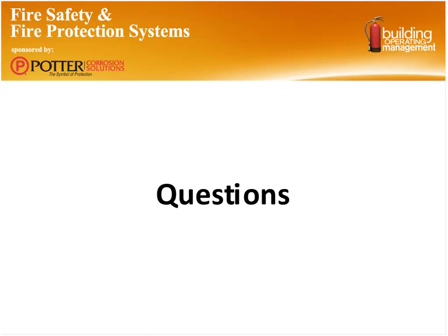One question that came through: who is supposed to inspect fire damper systems? Typically, there's two types. There are a couple of companies out there that are strictly what we call fire door, fire damper testing and inspection companies. They are kind of standalone, and that is their special niche. On the other side, there are traditional door companies, like rolling door companies and overhead garage door companies. A lot of them will have a division within them that tests fire doors, and most larger mechanical contractors will have what they call a balancing and commissioning group that will actually come in and do fire damper and fire stopping inspections. Okay, great, thanks.